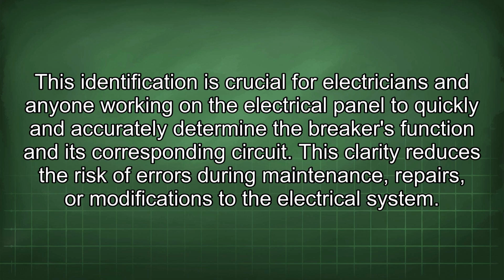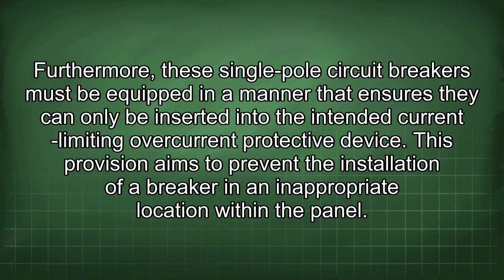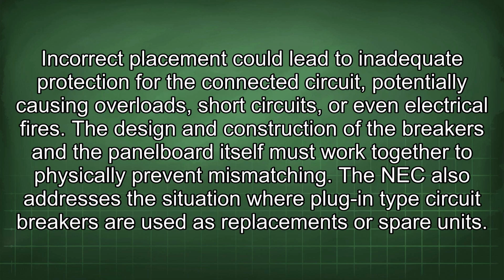This clarity reduces the risk of errors during maintenance, repairs, or modifications to the electrical system. Furthermore, these single-pole circuit breakers must be equipped in a manner that ensures they can only be inserted into the intended current-limiting overcurrent protective device. This provision aims to prevent the installation of a breaker in an inappropriate location within the panel. Incorrect placement could lead to inadequate protection for the connected circuit, potentially causing overloads, short circuits, or even electrical fires. The design and construction of the breakers and the panel board itself must work together to physically prevent mismatching.